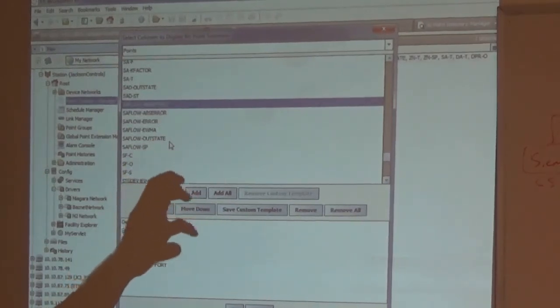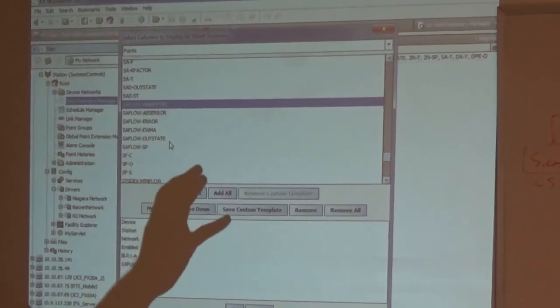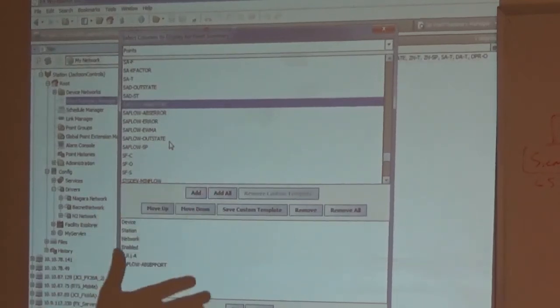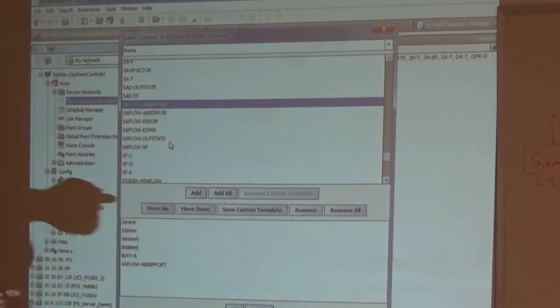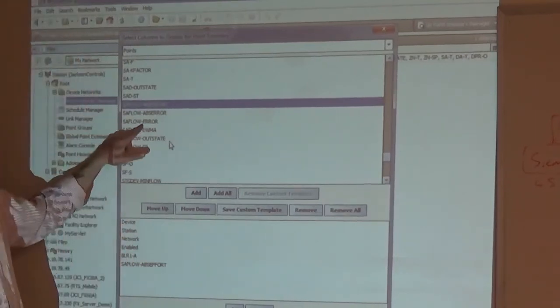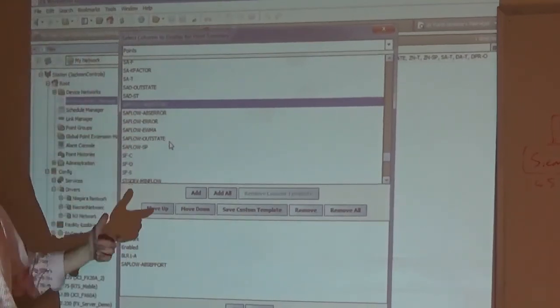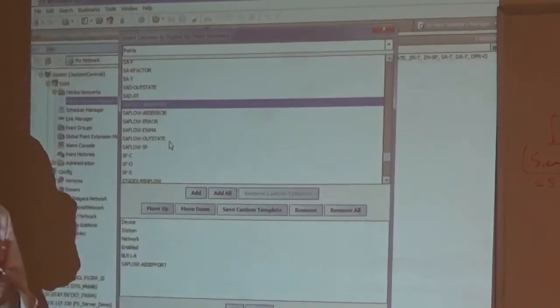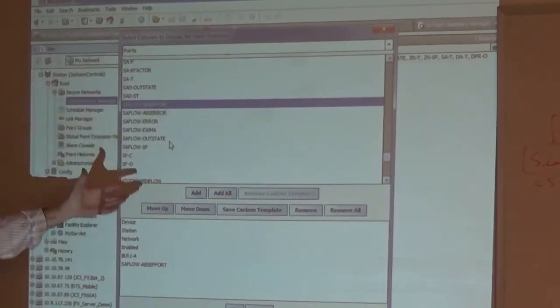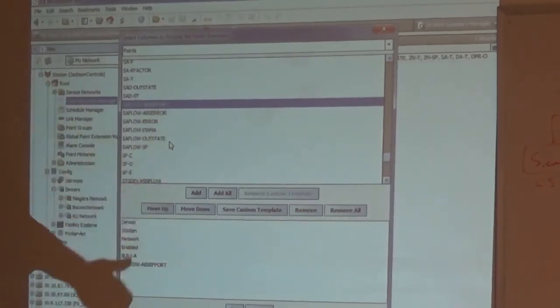The further they are from one, the less in control you are. So there's flow, heating, point - you might monitor, bring that point in and monitor error for flow. You'll know, guess what, if I got a value higher than one, there's something wrong. Maybe that damper is slipping a little bit, or the actuator isn't tightened down, or something like that. Things that wouldn't trigger an alarm, it's just there, right? So you can see that.